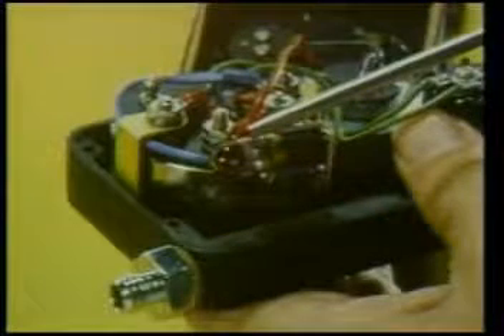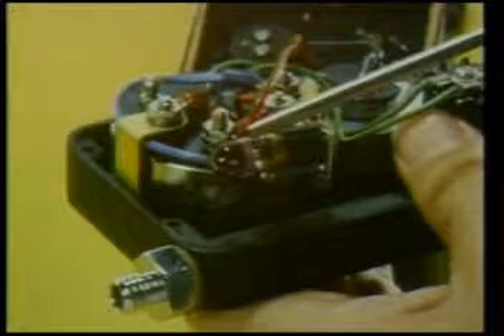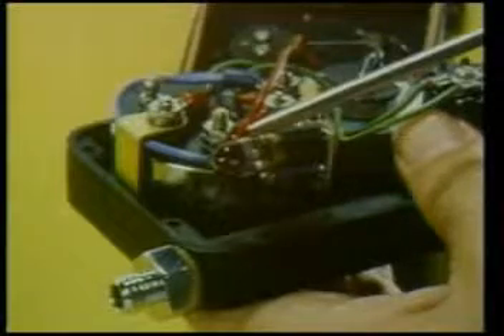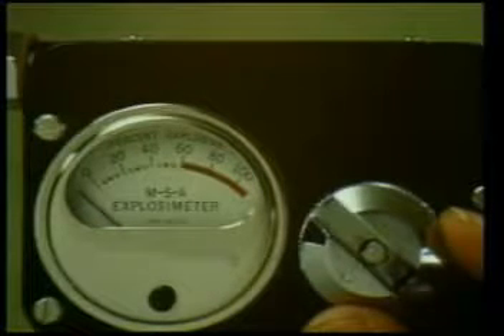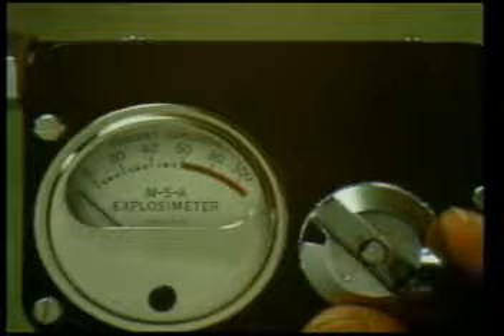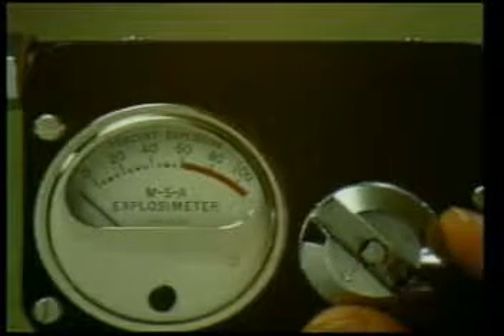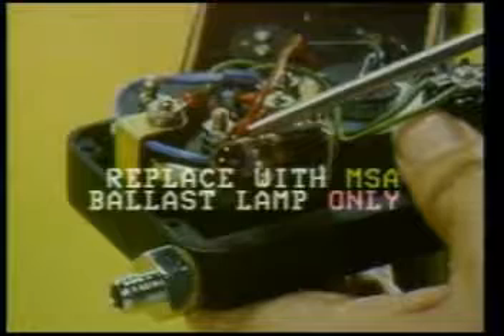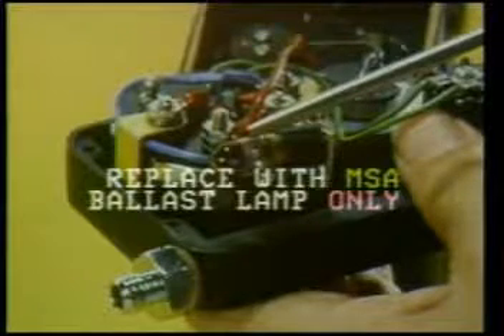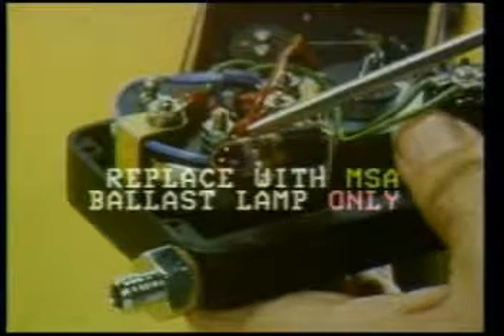Another replaceable component in the electrical system is the ballast lamp. Its job is to keep the circuit stable. The lamp should last the life of the instrument. However, if it does burn out, the meter needle will go downscale and stay there, despite attempts to adjust the zero control. The lamp must be replaced by another ballast lamp. These units are made specially for MSA, and a commercially made lamp must not be substituted.